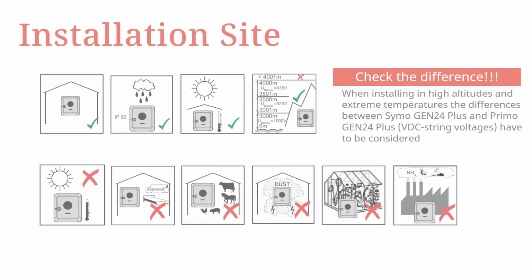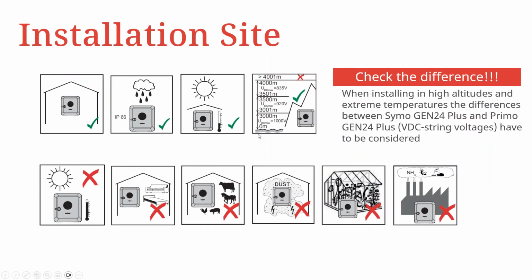Good. So just shedding more light on what I've just mentioned earlier. As you can see, our inverters are IP66, meaning that they have ingress protection against raindrops or jet water and sunlight, but it is advised to have them installed under shade, possibly under the PV shade. So that's good enough.